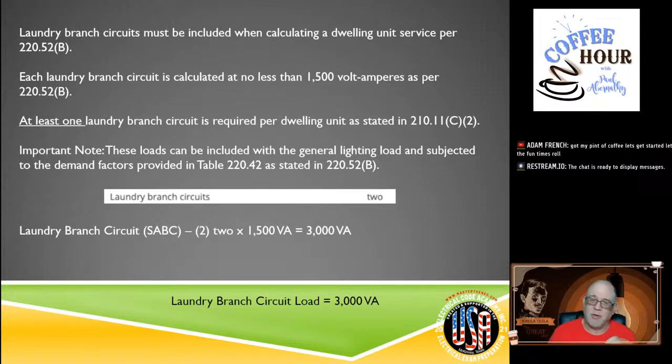Now, even though the code says you only need 1, notice that it's very specific here. It says for each. So we have 2. So it's 1,500 VA each, right? So laundry circuits, 2, 1,500 VA, that's 3,000. So there you go. There's 3,000.